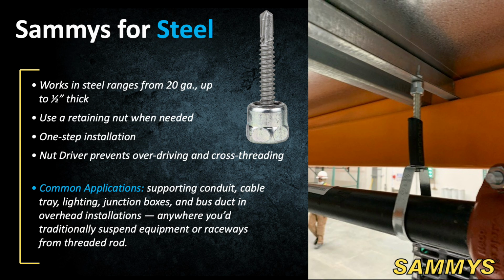For steel, Sammys anchors use a TEKS drill point so they can drill, tap, and fasten in a single operation without pre-drilling. They're designed to work in steel thicknesses ranging from light gauge up through heavier structural members. When required, you can use a retaining nut on the backside, but in many cases the formed threads in the steel provide the holding power on their own. You'll see these used on I-beams, bar joists, channel, and structural steel whenever you're hanging threaded rod for electrical supports.